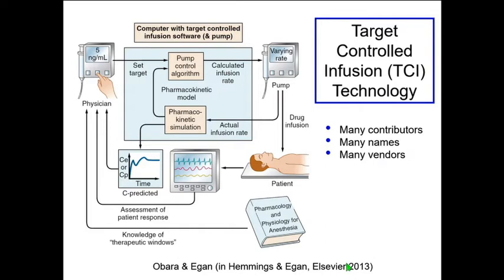So the pump calculates the infusion rate and then gives it to the patient. The pump has to report back what it gave. Why is that? Well, it's because the pump can't perform exactly what it was directed to do. The pump has certain limitations, a maximum infusion rate and so on. So the computer algorithm will say, I want you to give a bolus right now, then an infusion like this, then start a new infusion at this rate. The pump tries to approximate those instructions, so it has to report back to the algorithm what the actual infusion was.